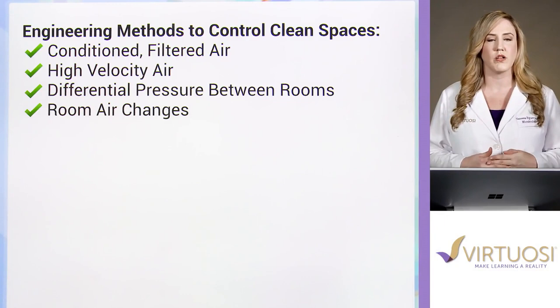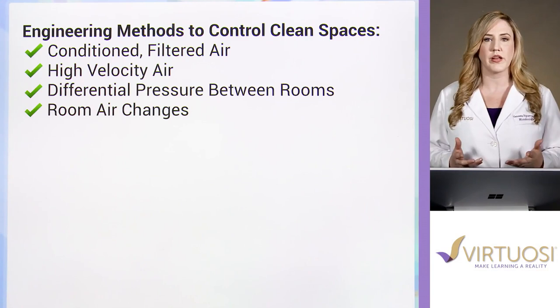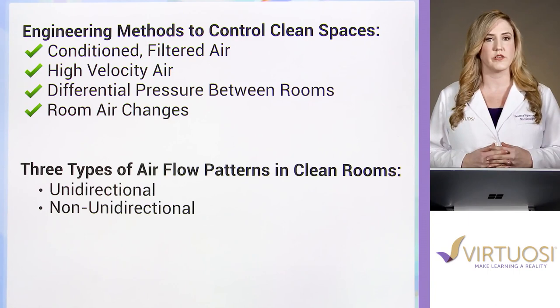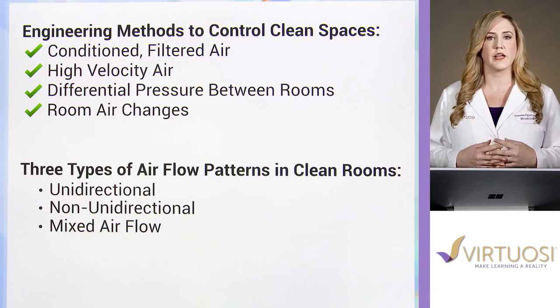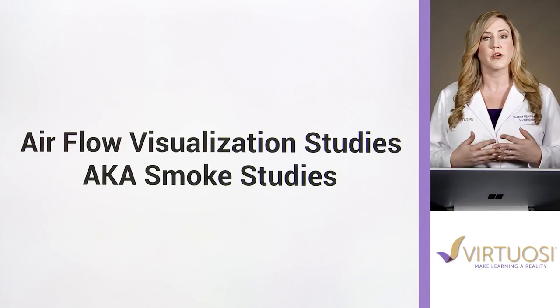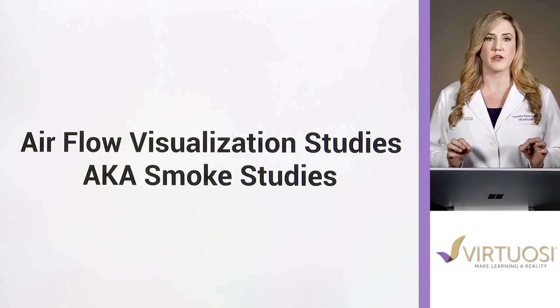Engineering methods provide the ability to maintain control of our clean spaces. Airflow in clean rooms can be classified into three patterns: unidirectional, non-unidirectional, and mixed airflow. Absolute measures of airflow velocity and exchange rates per hour, although important, may not be as useful as visualizing and evaluating air movement within the operating environment. Therefore, it has become an industry best practice to evaluate airflow through the creation and implementation of studies utilizing visible smoke.